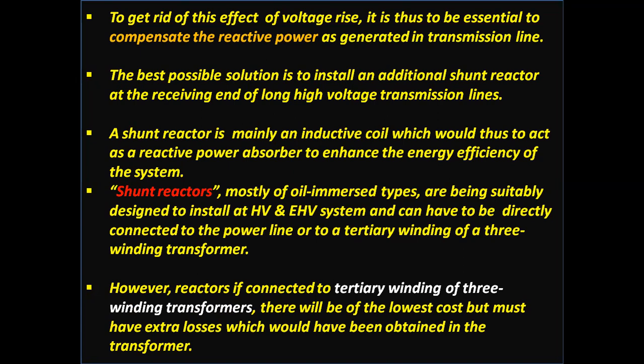However, reactors connected to the tertiary winding of 3-winding transformers will be of the lowest cost but will have extra losses in the transformer itself.